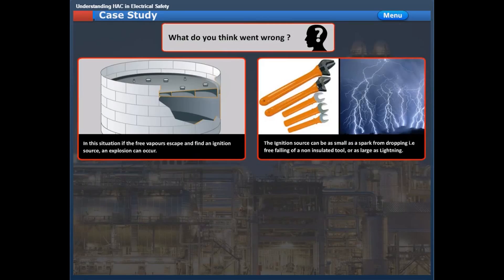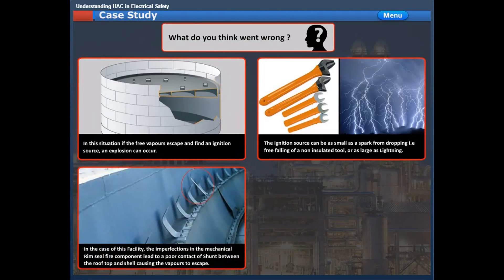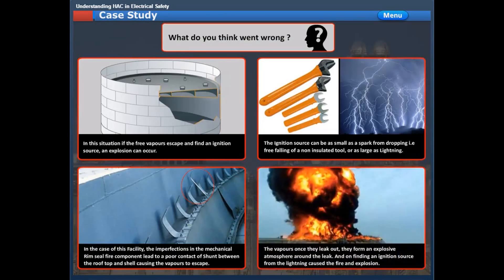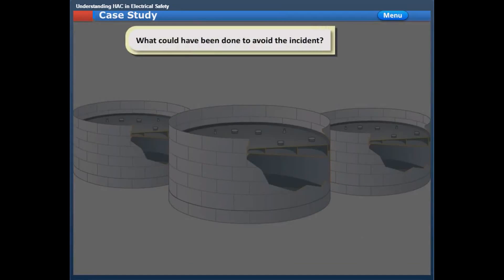The ignition source can be as small as a spark from the free falling of a non-insulated tool. In the case of this facility, the imperfections in the mechanical rim seal fire component led to poor contact of the shunt between the rooftop and shell, causing the vapors to escape. The vapors, once they leaked out, formed an explosive atmosphere around the leak, and on finding an ignition source from the lightning, caused the fire and explosion. What could have been done to avoid the incident?